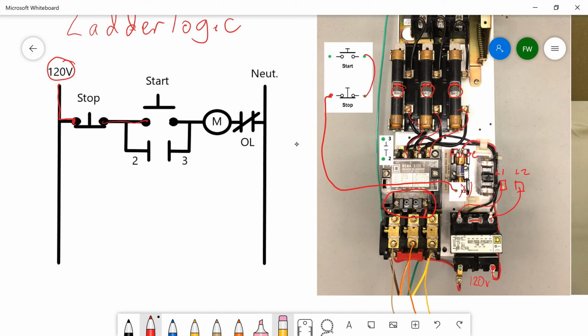As we go along, we're going to check these wires off, and we notice that it also hooks up to the number 2 on our contactor. So let's take it out of that side of our stop. It could also be from our start. They're all the same wire, but as long as it's coming from the other side of our stop switch, we're good. Okay, so now we've got this taken care of on our ladder logic and on our schematic diagram here. We need to take care of the other side of our start switch. So now we can go from our start on this side and we can take that over to 3.